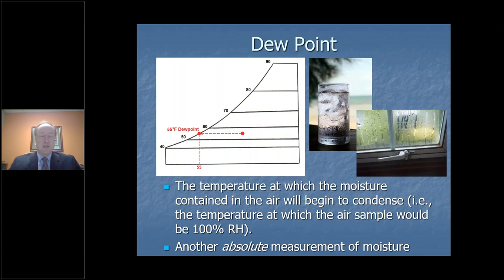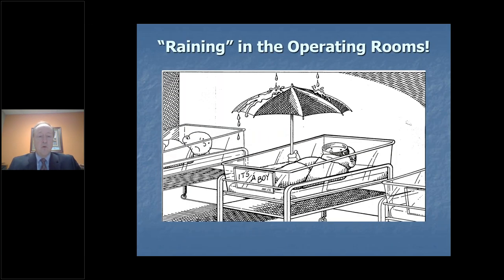And that's why we need to understand the dew point, because if we know how cold any of the surfaces may be in our operating rooms or throughout the hospital, we know that we need to keep the dew point temperature of the air in that environment lower than the surface temperature. And I usually strive to keep the dew point temperature in that environment at least 5 degrees lower than any surface temperature that I might encounter.